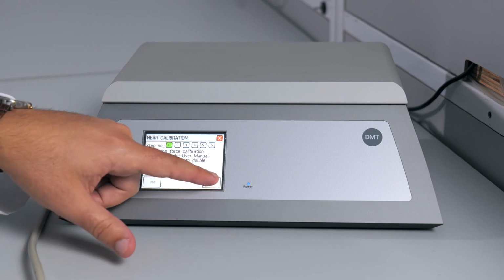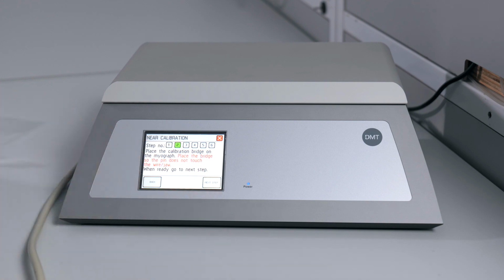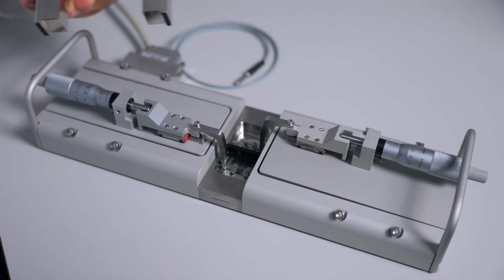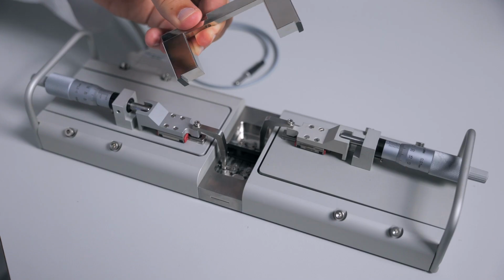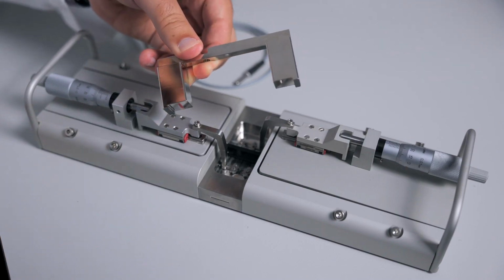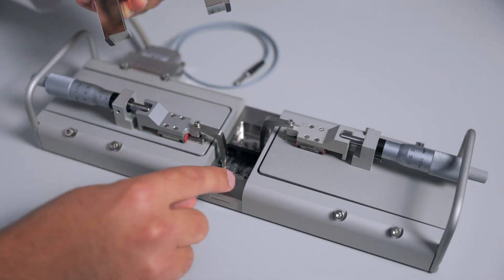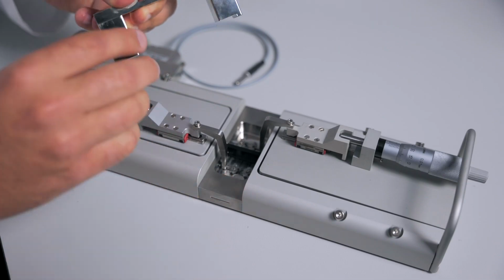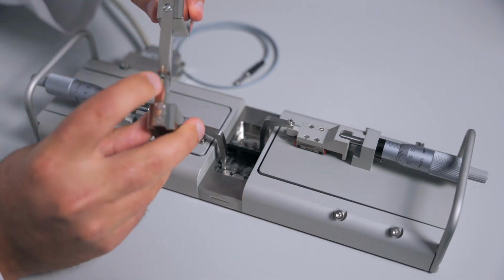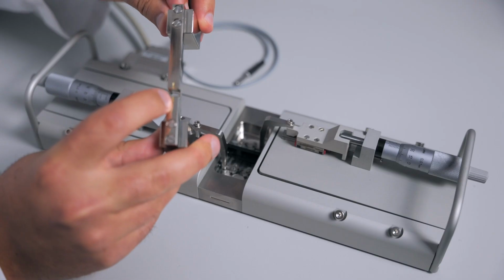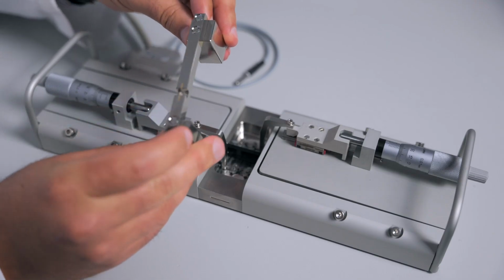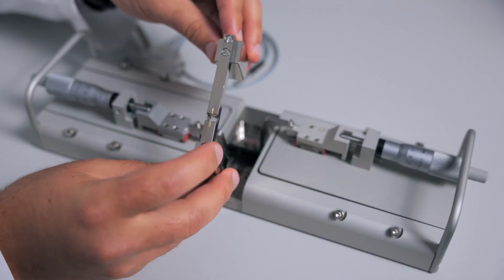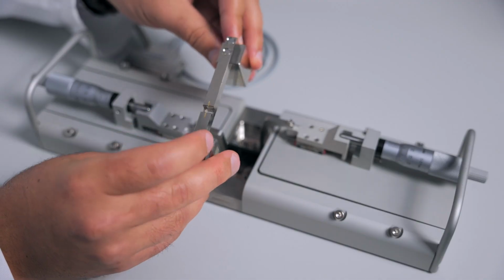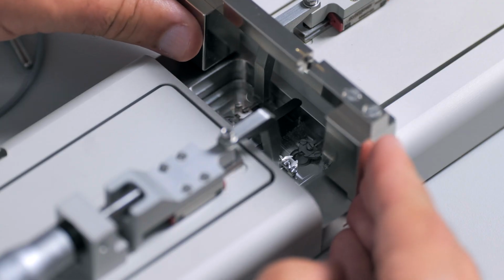You can select next step to go to step 2, which asks you to place the calibration bridge and T-balance on the myograph. You will see that the calibration bridge has 2 feet, but these should both be on the chamber itself. You will also see that there is a hole with slots on the side, and this should go over the chamber that you're going to calibrate. So we'll place this over the near transducer.